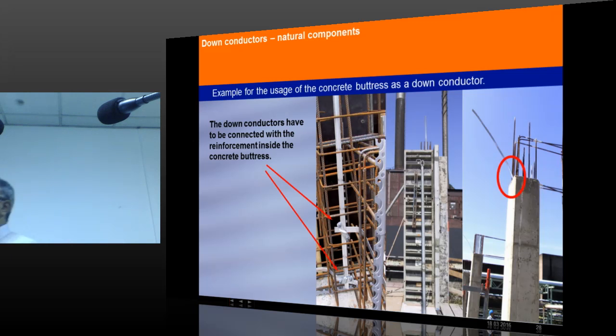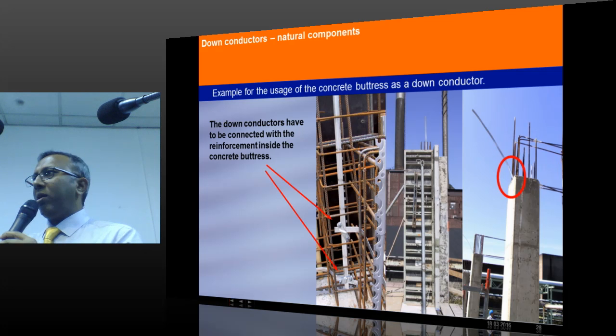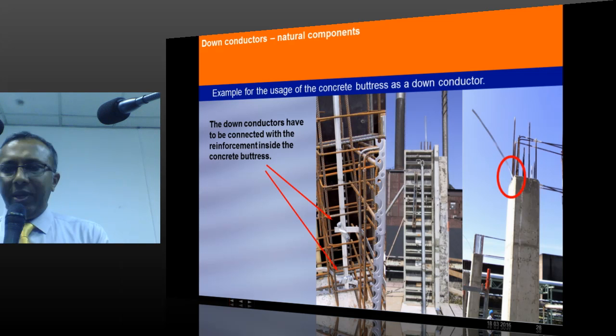One example: once IEC recommended this practice, that means you use your reinforcement, your structural steel, then the argument starts. Structural engineers will not accept it, because then you are doing something to the structure which gives the whole strength of the building. So, as a solution, the standard recommends that you can also run a separate conductor. You see here, there is a separate conductor. This separate conductor will also do the job of a down conductor, or all the previous conditions can be skipped.